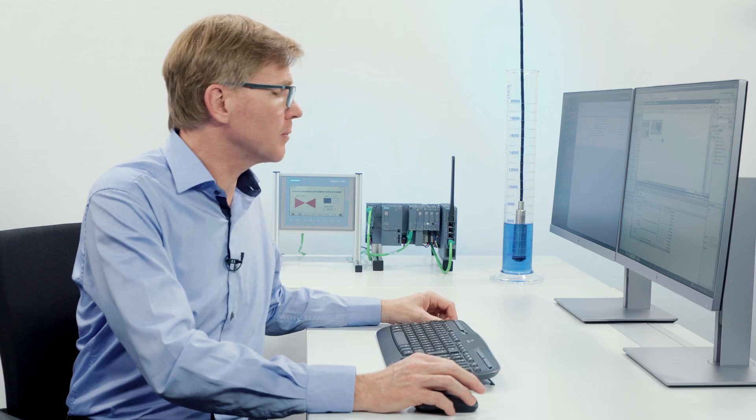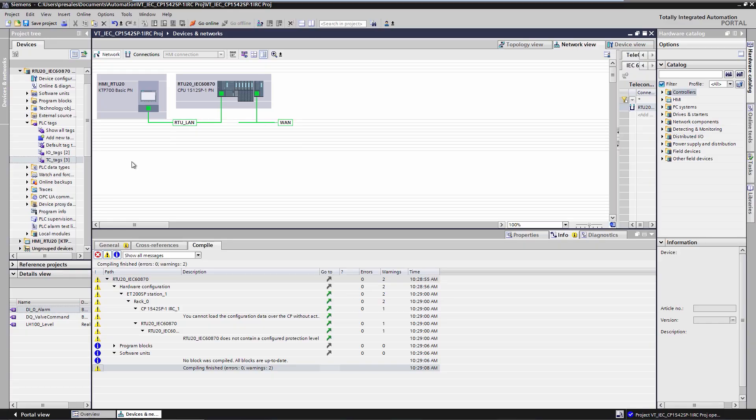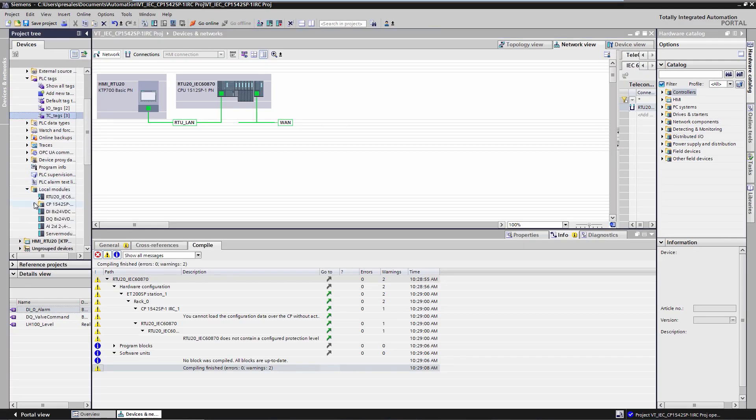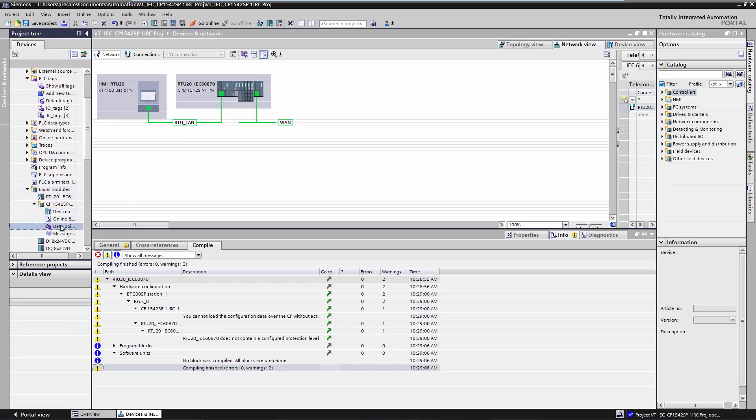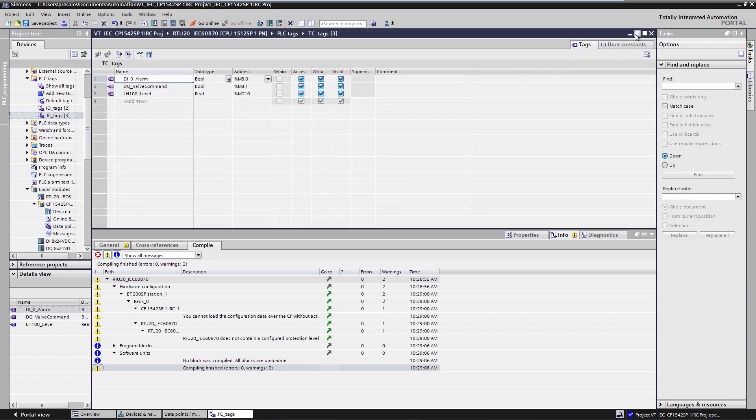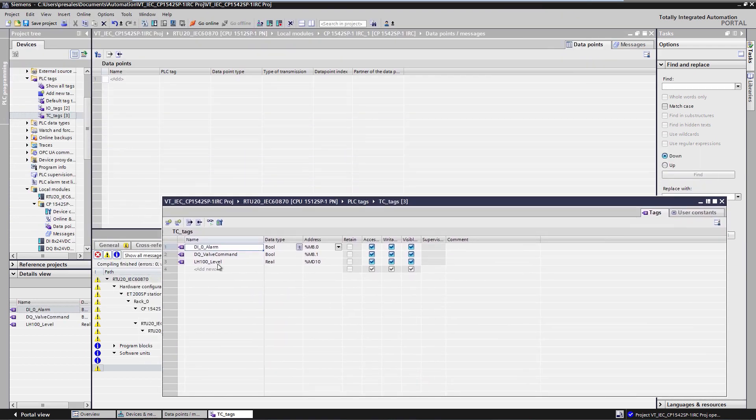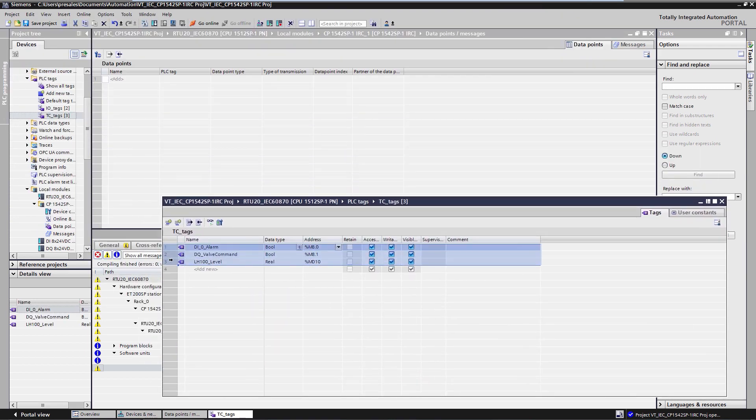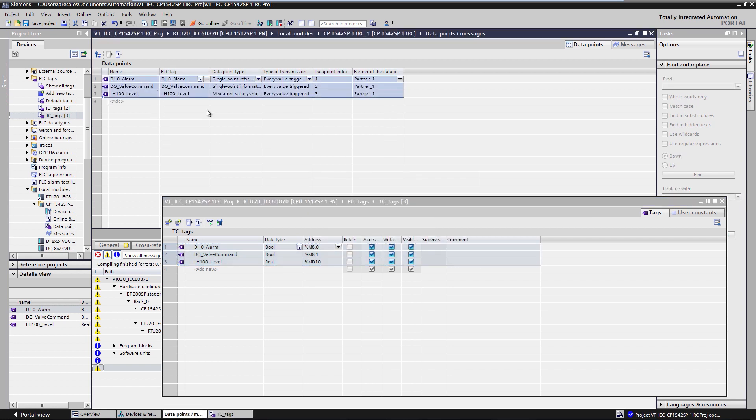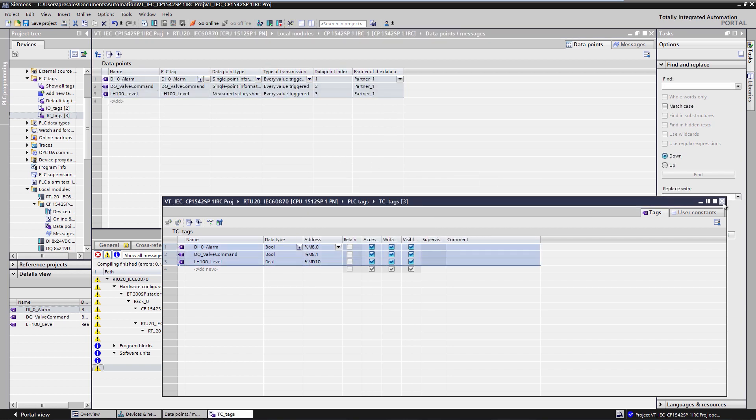We now switch to the data point editor of the CP. I open the PLC tag table or the DB on the CPU. I simply drag and drop the CPU tag that is to be sent to or received by the IEC master into the data point editor. Thus, the process values are transmitted on this tag as IEC data points from RTU to master or from master to RTU.